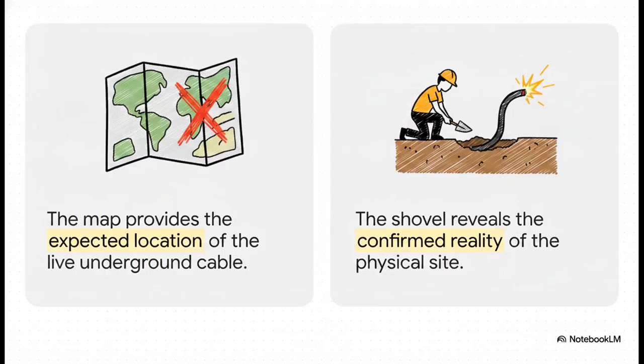No way. Think of it like being a bomb disposal technician. A bomb squad would never use a mechanical digger to blindly scoop into the ground just because a schematic says there's probably an explosive down there, right? The stakes with a live 230 kilovolt transmission line are genuinely comparable. The map gives you the expected location, but the shovel gives you the confirmed physical reality. You absolutely must probe by hand to find the physical truth before anything mechanical gets anywhere close.